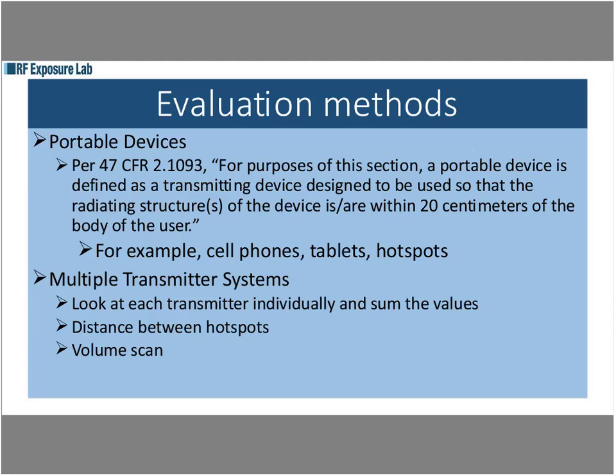Multiple transmitter systems, this is kind of a tough one. With SAR, we still look at each transmitter individually. We do not do the testing with multiple transmitters operating at the same time. And then there are a couple of options. We either sum the values, and as long as we're less than the limit, we can consider that the worst case mode will pass the SAR requirements. So you meet the simultaneous requirements by summing the values.